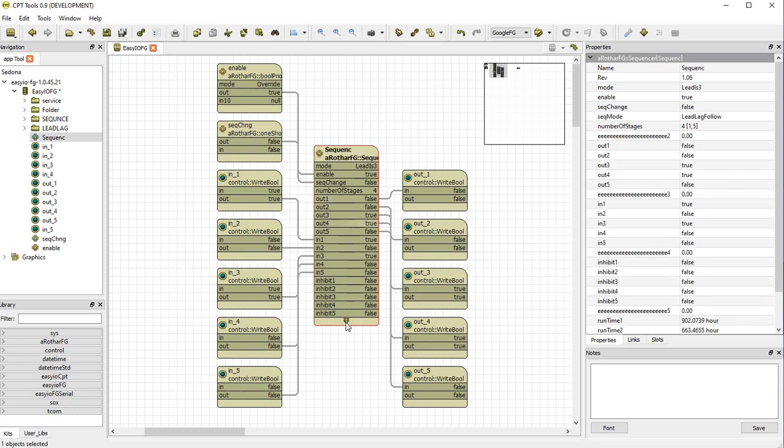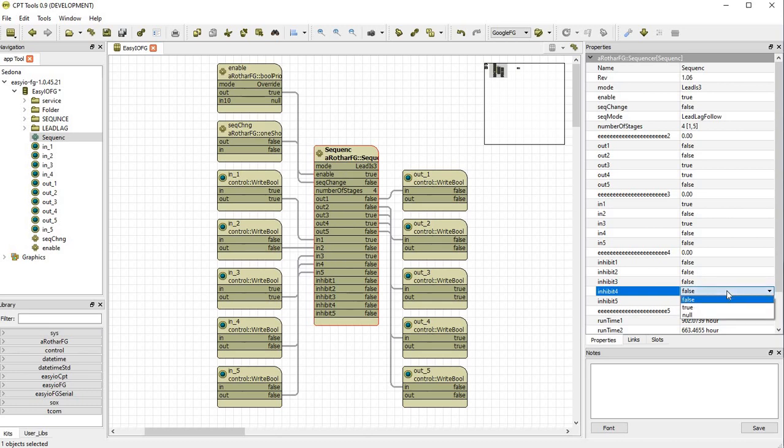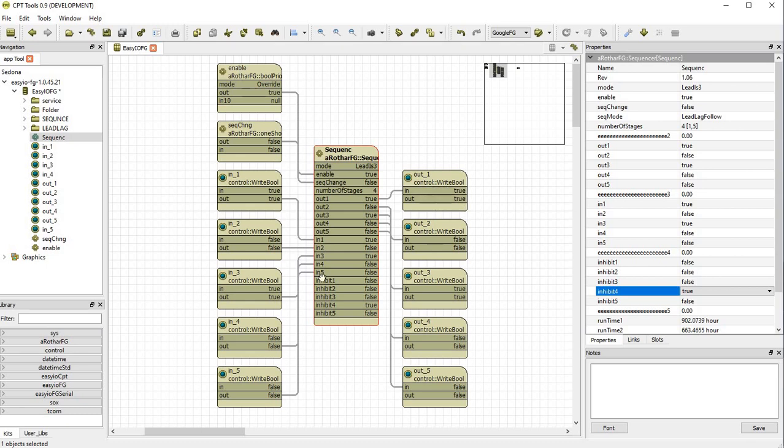So if we received a fault on equipment number four, four will turn off and one will turn on. This maintains the number of outputs running based on their availability.